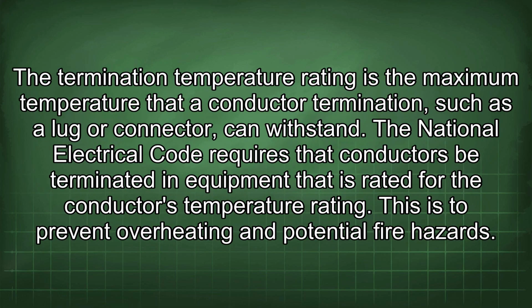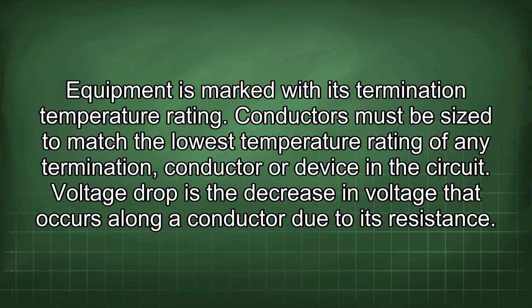The termination temperature rating is the maximum temperature that the conductor termination, such as a lug or connector, can withstand. The National Electrical Code requires that conductors be terminated in equipment that is rated for the conductor's temperature rating. This is to prevent overheating and potential fire hazards. Equipment is marked with its termination temperature rating. Conductors must be sized to match the lowest temperature rating of any termination, conductor, or device in the circuit.